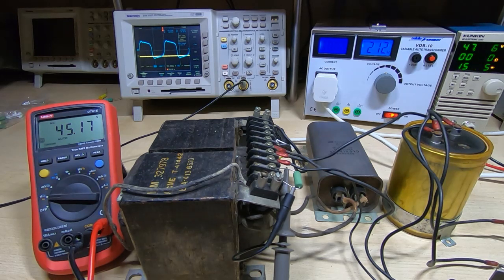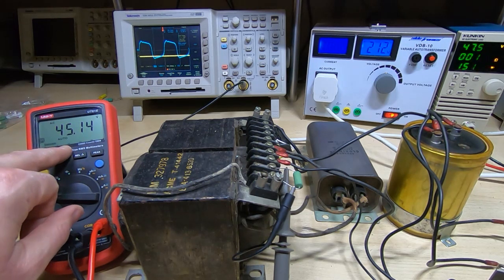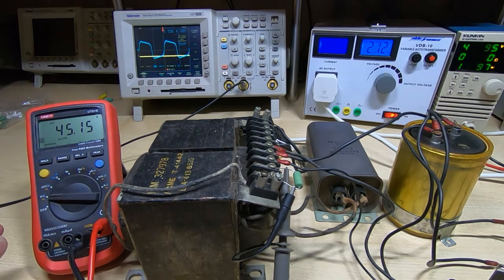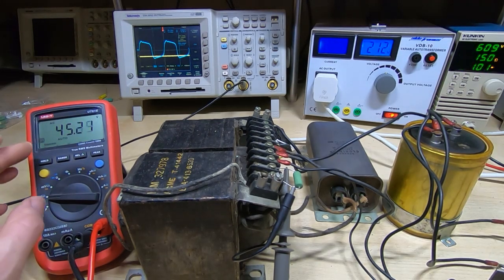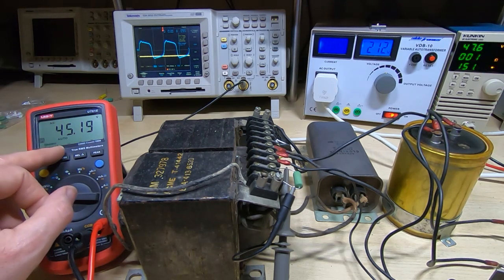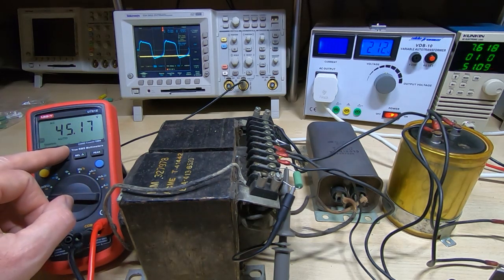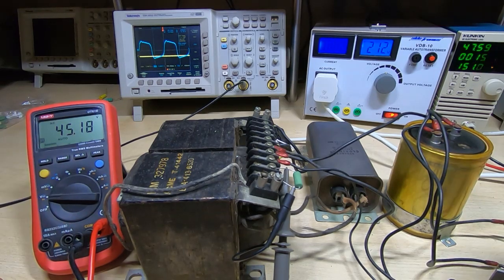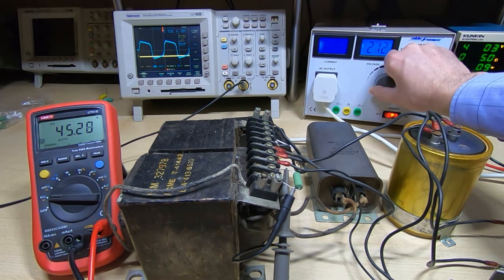increase any further either. And so what's happening here is the secondary part of the core is being forced into saturation very early on in the primary voltage cycle, and that means that it's running straight up into the saturation region. It reaches its peak voltage very early on, and the result is that the AC voltage is limited to a value dependent on the design of the transformer. So in this case it's limited to around 45 volts, and that 45 volt limitation is because to go above that the core flux would have to rise further, and of course the core flux cannot rise further because the core is saturated.